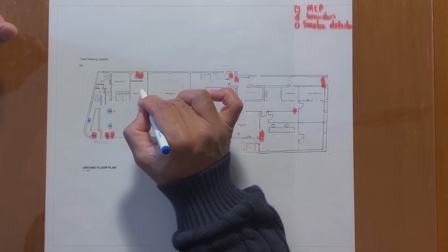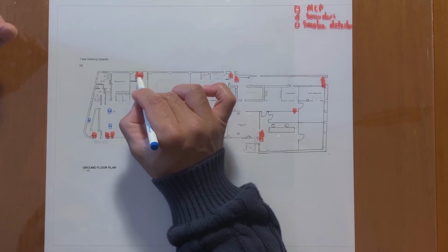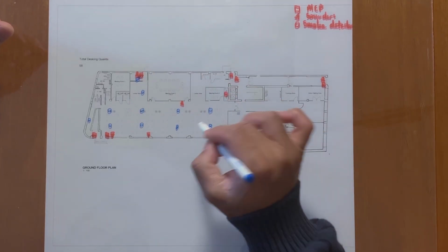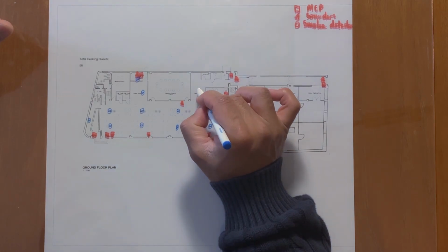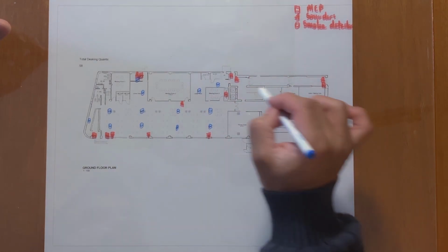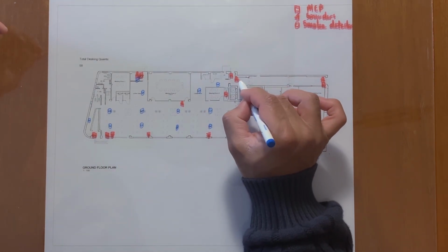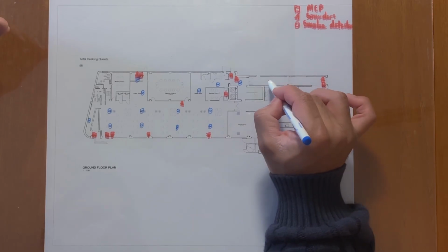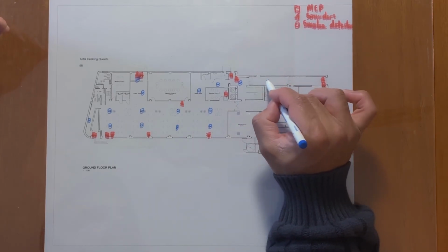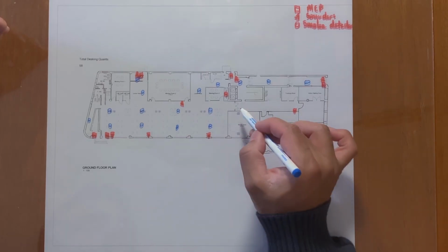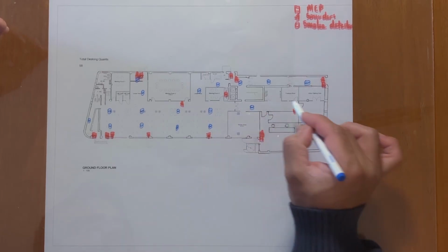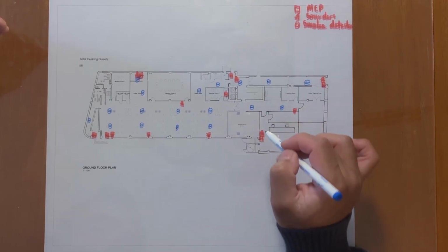And then this will probably have one here because that's all open, and then another one over there because that's all part of the escape route. Then going through here, this is all part of the escape route, so we'll have one here and maybe down there. Again, this is also part of the escape route, so down there. This is a separated area, so we'll have to have one in there and again in there. Coming this way, we need to have a detector in here. Maybe we'll have 2 along that passage.